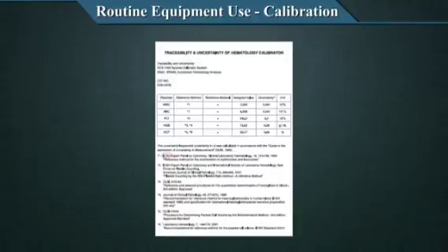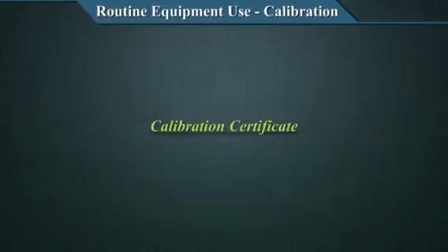And it's a very important resource that you have to document and keep filed, along with the expiry date and lot number. All these things will be mentioned on your product insert, and this should be looked through, understood, and also filed. And all these components should be understood before you embark upon the calibration. If there is an uncertainty which is beyond the acceptability of your laboratory, you can always refuse to use this kind of a calibrator.